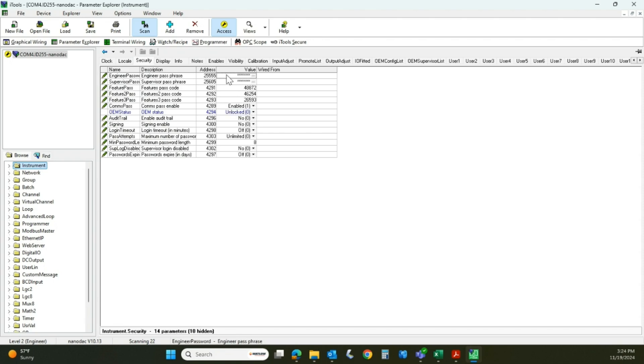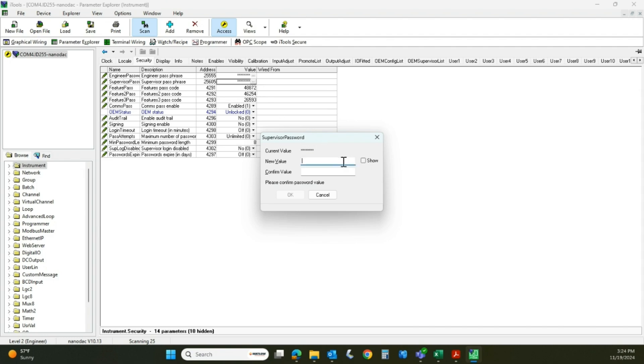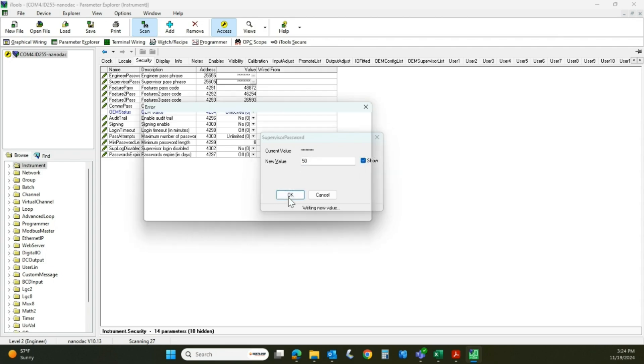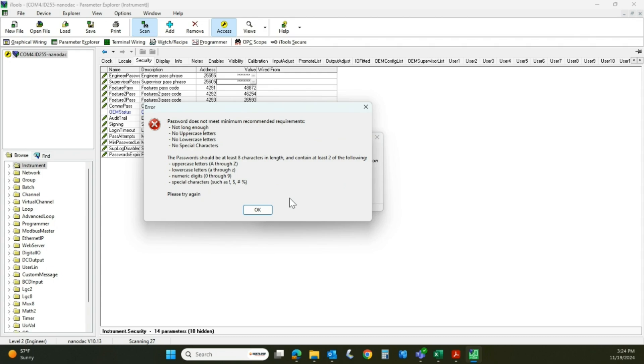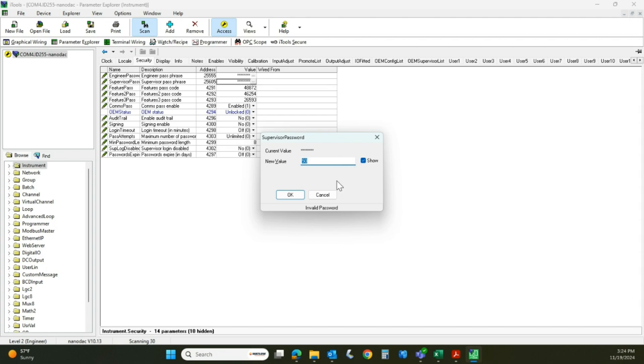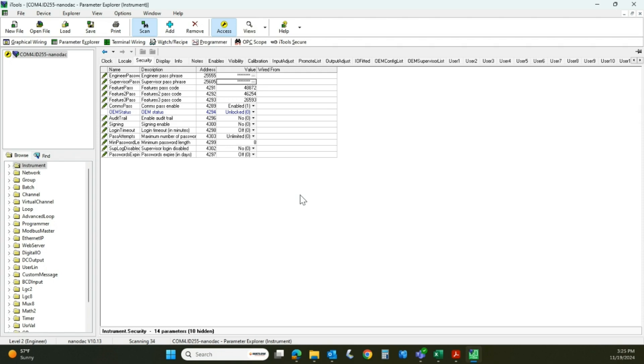When you go to Security, there's your engineering passphrase and your supervisor passphrase. My instrument did not have a supervisor level — but that's easy to set up. Hit the three little dots and give it a supervisor password. Note that the nanodak has a minimum password requirement, so if you try to enter something it doesn't like, it will reject it. Enter a valid password and now we have a supervisor password set.